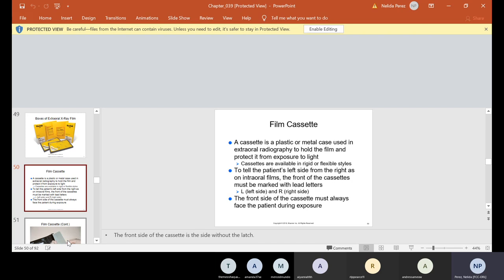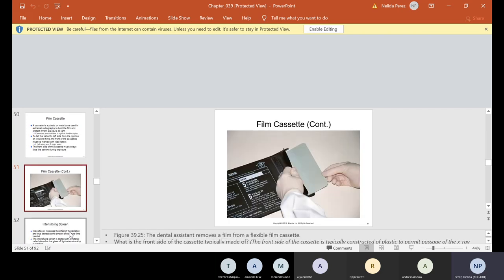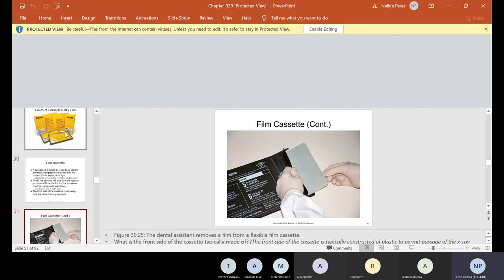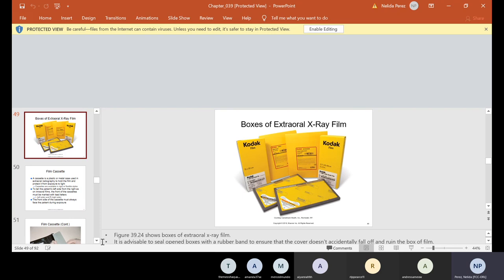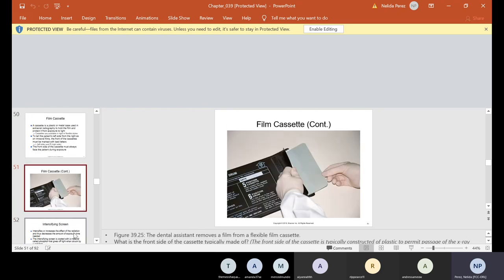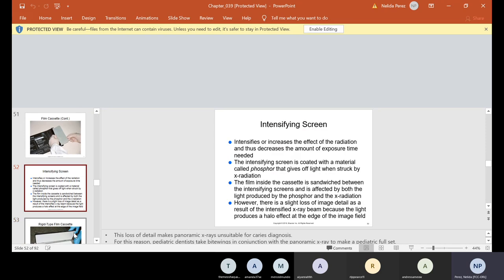The front of the cassette must be marked with letters like L for left and R for right, and must always face the patient during exposure. Cassettes are available in rigid or flexible styles. Inside the cassette are intensifying screens that intensify or increase the effect of radiation, thus decreasing the amount of exposure. The intensifying screen is coated with a material called phosphor that gives off light when struck by x-radiation. The film inside the cassette is sandwiched between the intensifying screens, affected by both the light produced by the phosphor and the x-radiation.